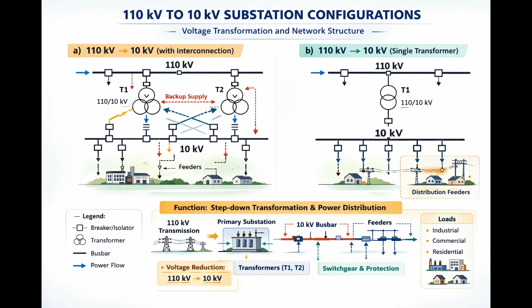and operationally safe. Now examine the busbar system in large primary substations. When the substation supplies many medium voltage feeders, the internal busbar arrangement becomes critical for reliability. One common solution is a two busbar system with two transformers. In this scheme, each transformer feeds its own busbar section. Feeders are divided between the two sections.